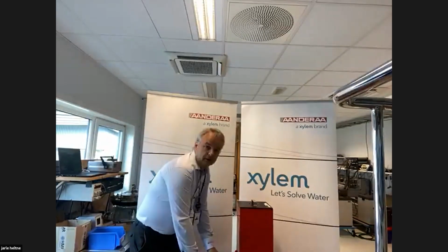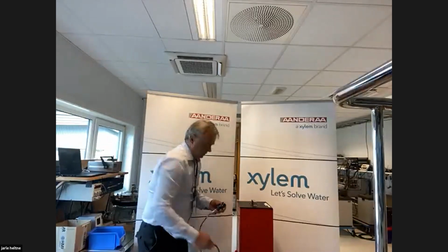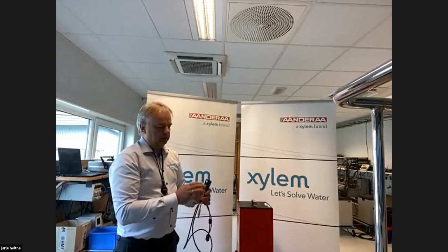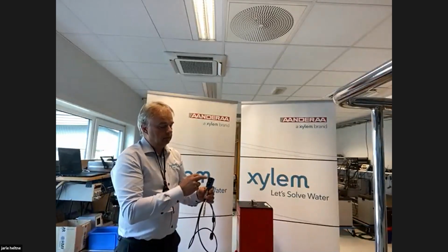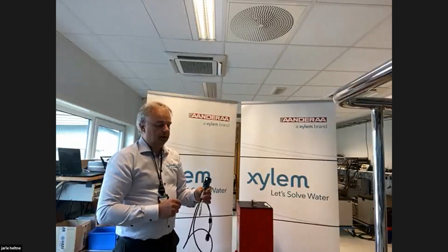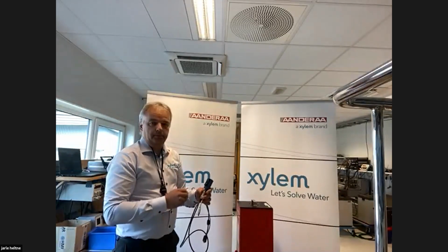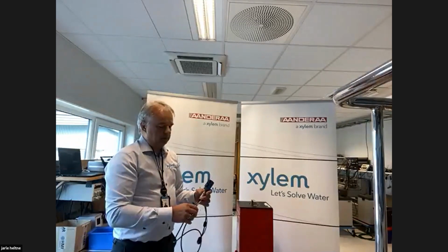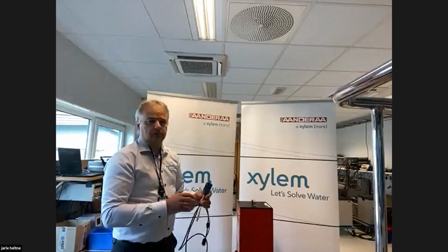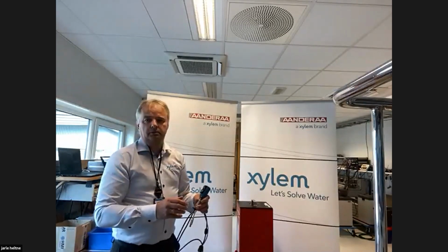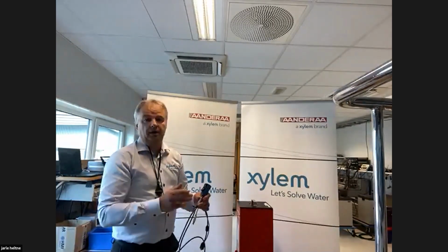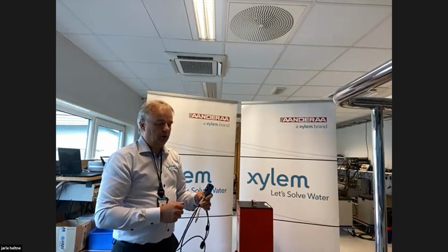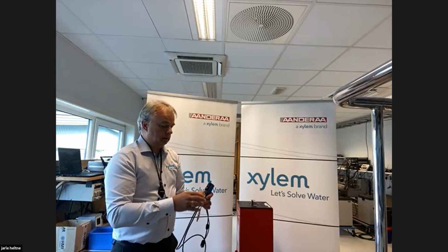Before I hand it back to Anders, I will tell you a little bit about the maintenance needs for this sensor. There are very low maintenance needs, but since this is an optical sensor, you need to keep the windows clean. This is best done using a brush, a soft brush or similar. But if there is a lot of fouling on the sensor when you recover it, we recommend putting the sensor in a vinegar solution overnight. Then it will be much easier to clean. And just make sure that you don't use any sharp object to clean the windows.